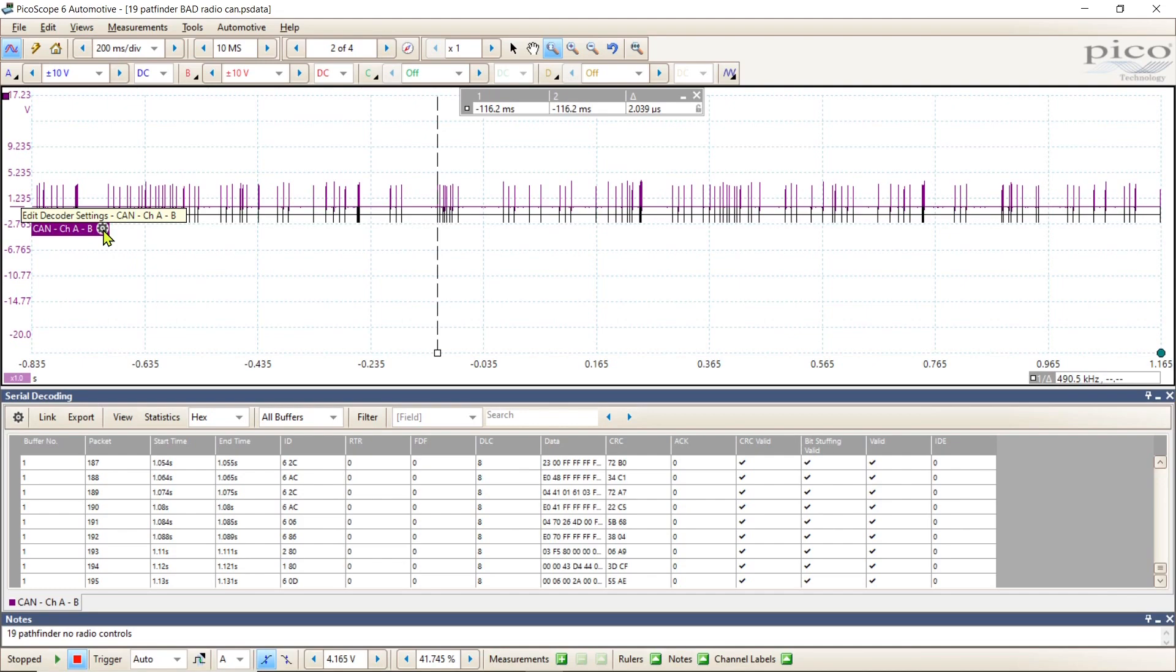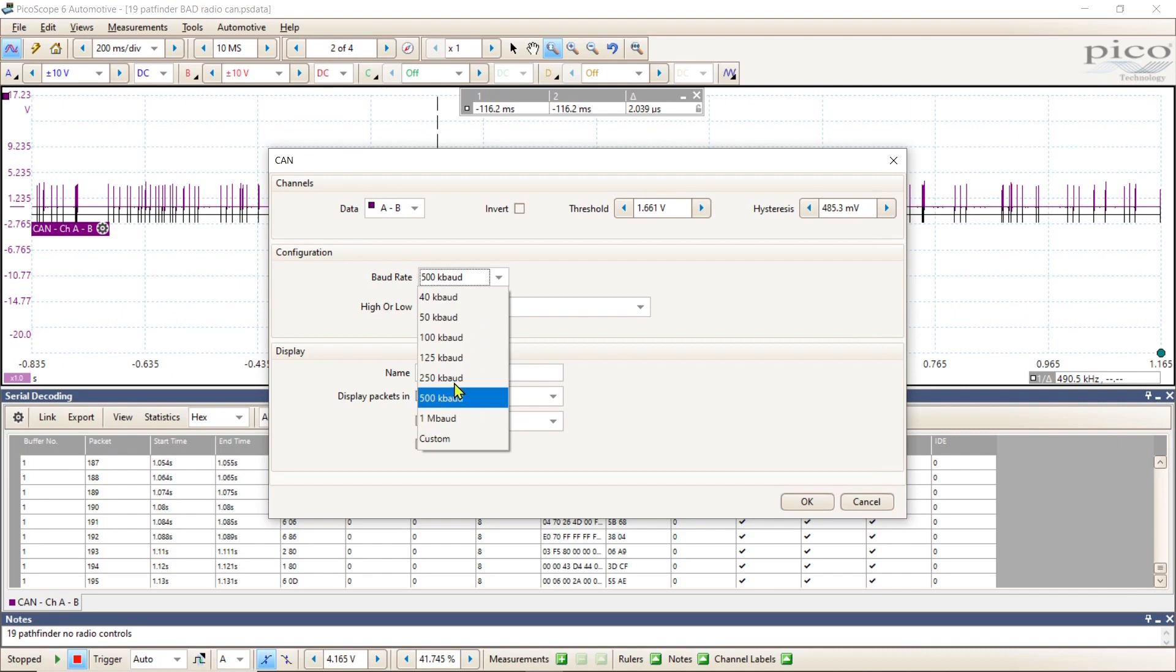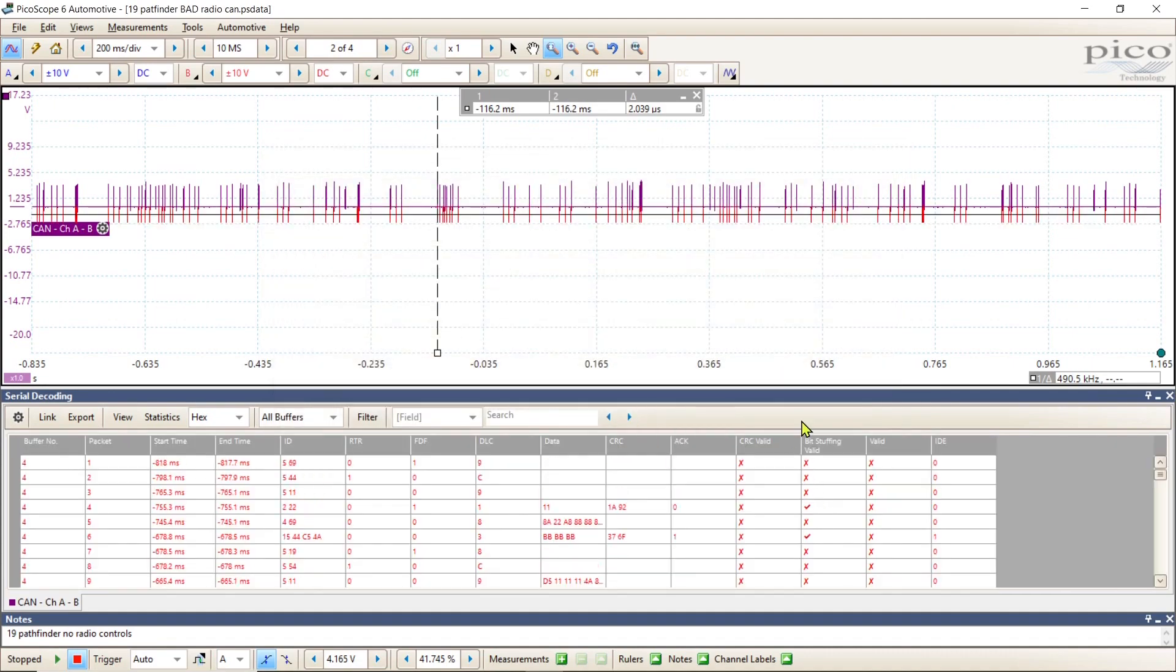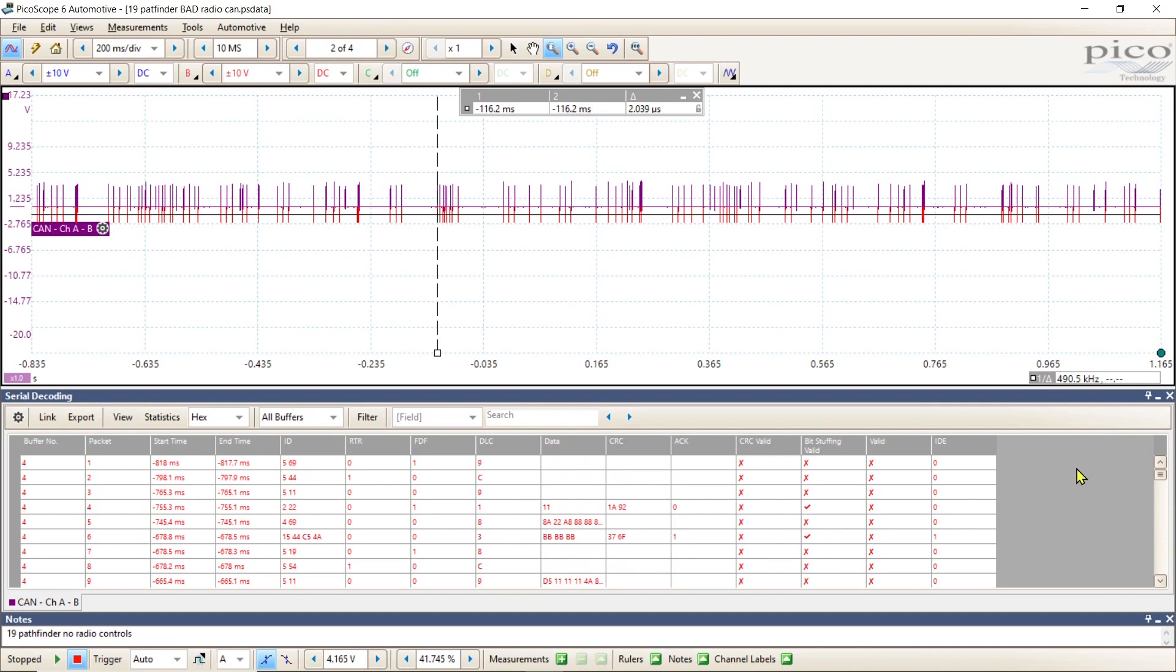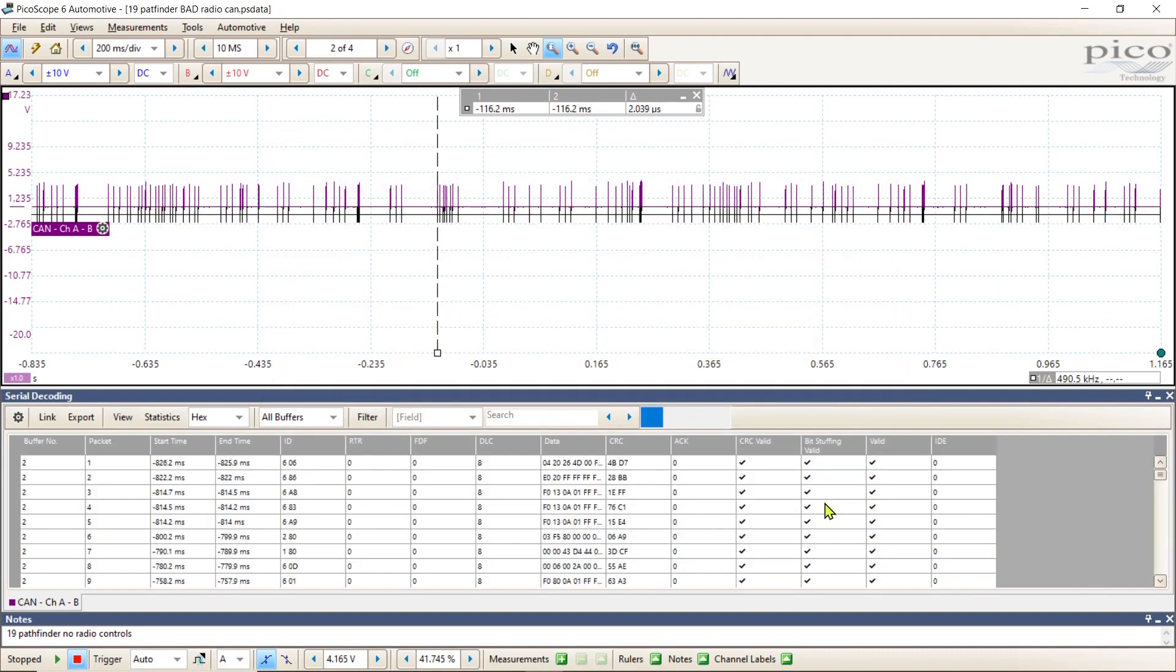With these control units, nothing on this network says I'm bad. Let me show you real quick if we made a boo-boo or if the network was bad. Let's pretend that I click 250 - we know it's 500 but I'm going to put it on 250. Now look at that. If you pick the wrong speed, you're going to get a whole bunch of problems here. Let's say if I had picked the correct speed and I got all this gibberish, all these X's, I would now be looking more at the signal versus powers and grounds. Without good packets of data, a control unit is blind - it can't do anything. Let's go back to my good - go back to 500 and hit okay.